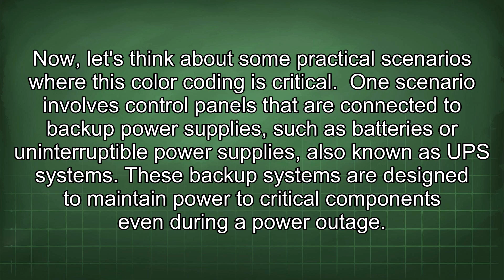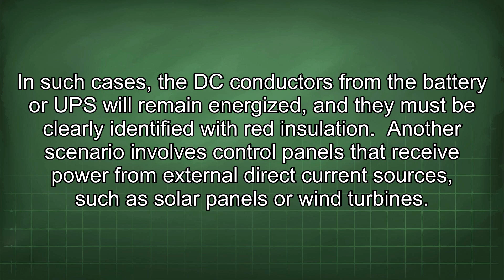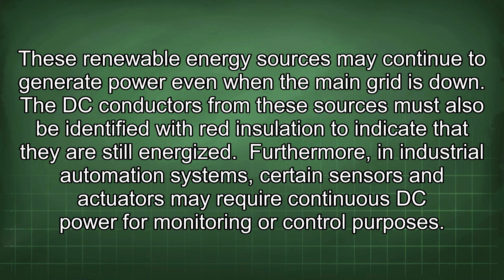Another scenario involves control panels that receive power from external direct current sources such as solar panels or wind turbines. These renewable energy sources may continue to generate power even when the main grid is down. The DC conductors from these sources must also be identified with red insulation to indicate that they are still energized. Furthermore, in industrial automation systems, certain sensors and actuators may require continuous DC power for monitoring or control purposes. These components may be powered by an external DC power supply, and the wiring must be properly color-coded to prevent accidental contact with live voltage.